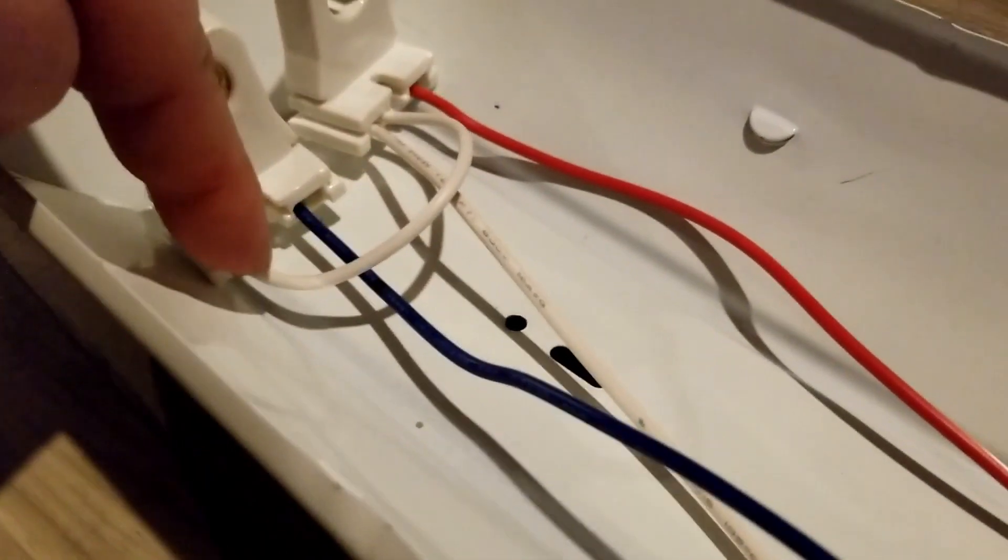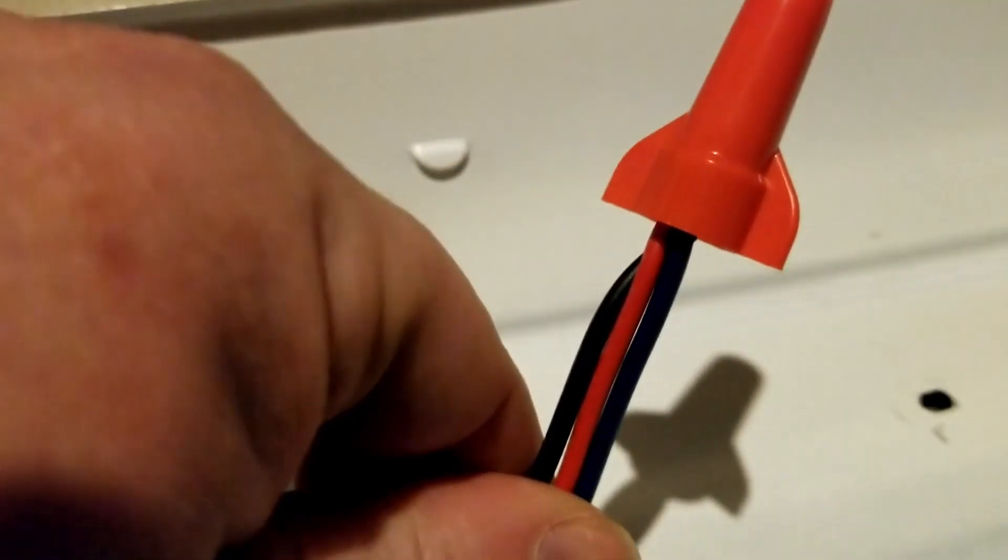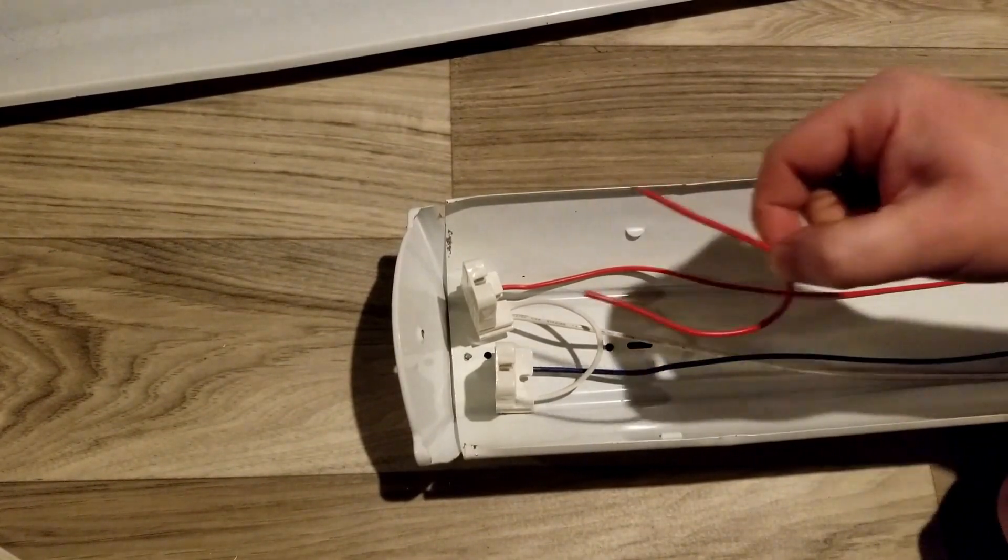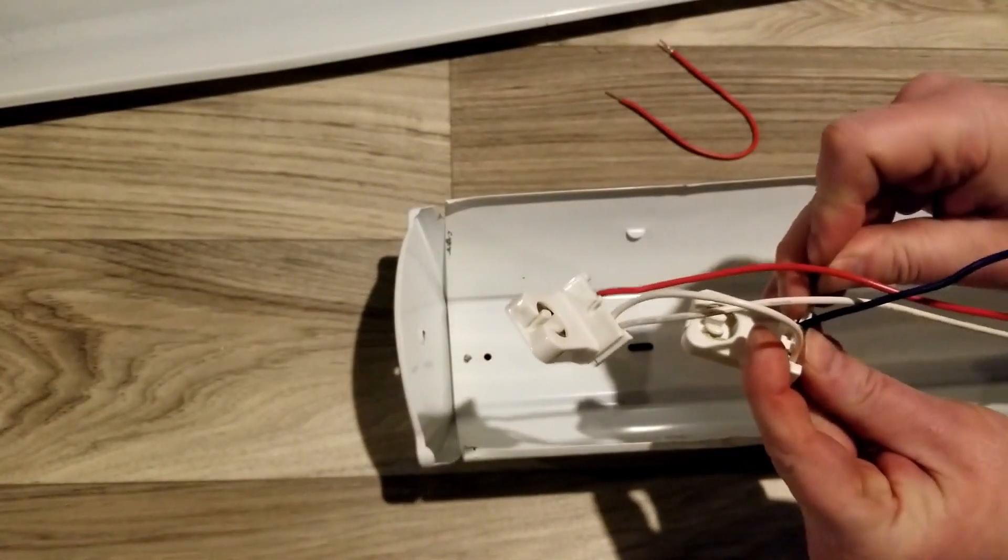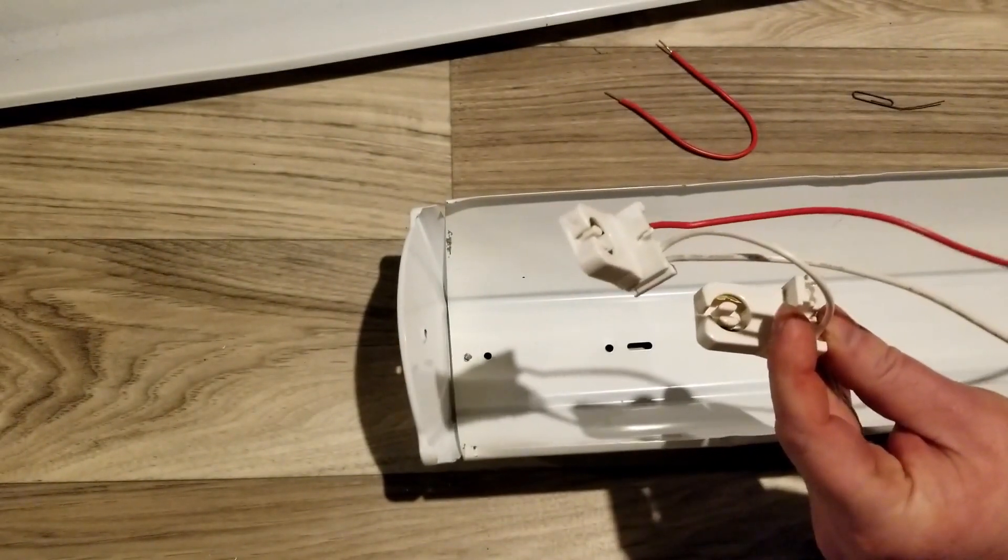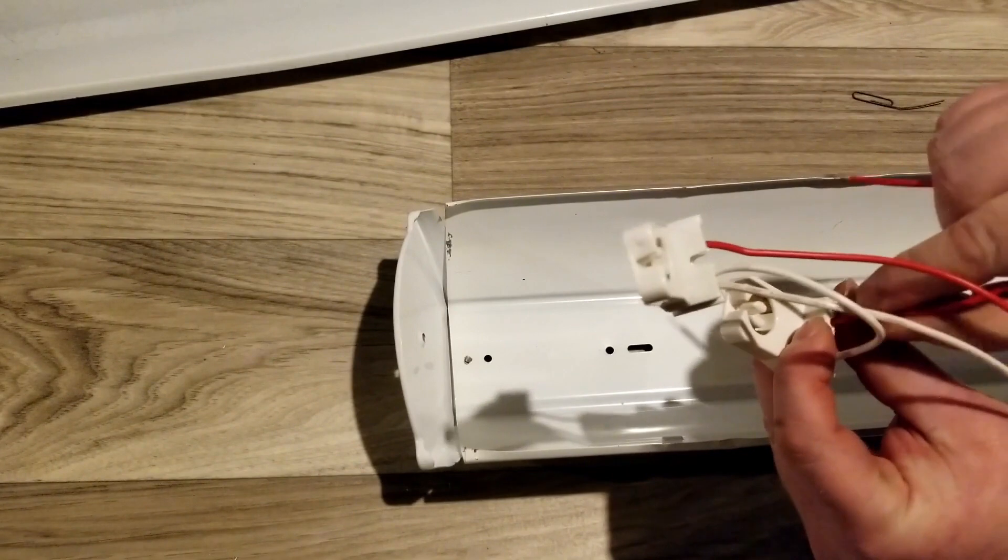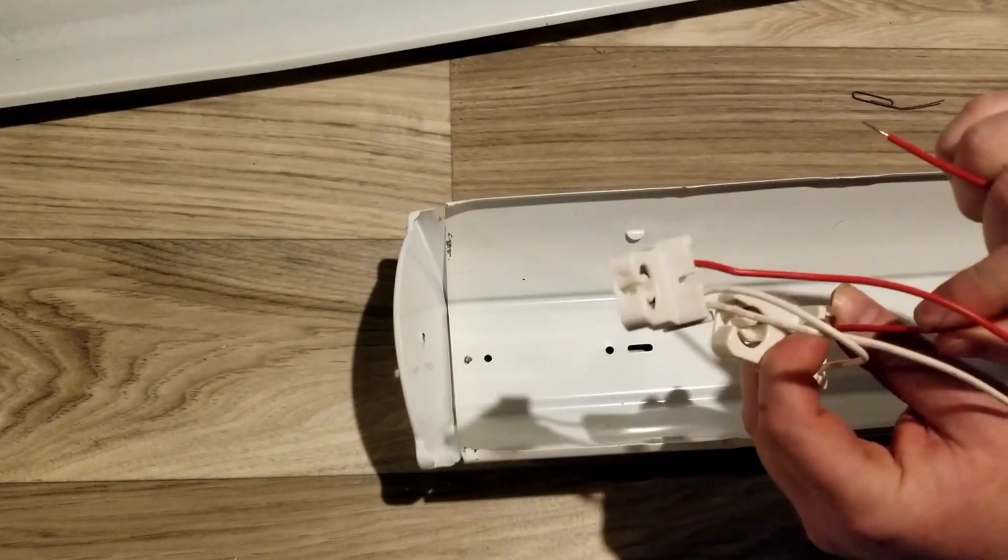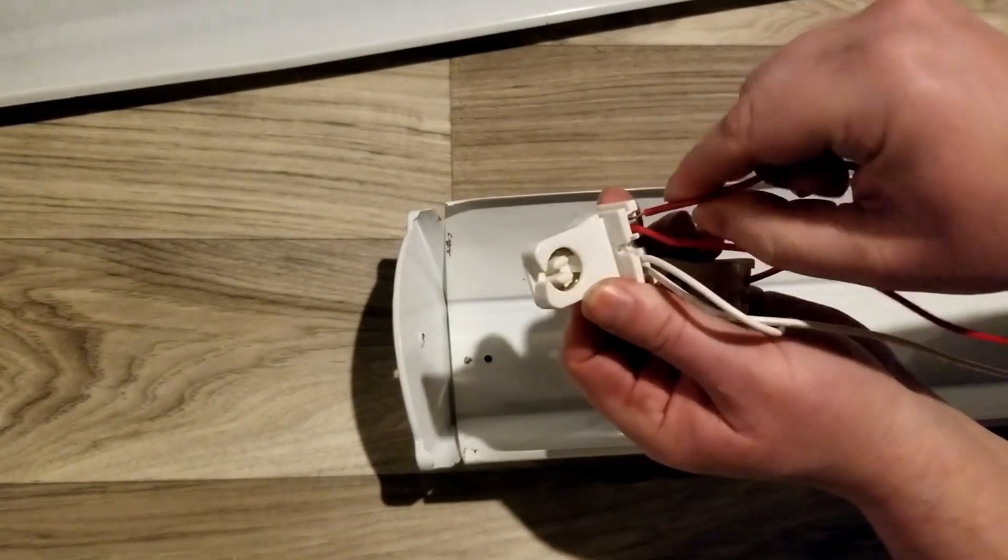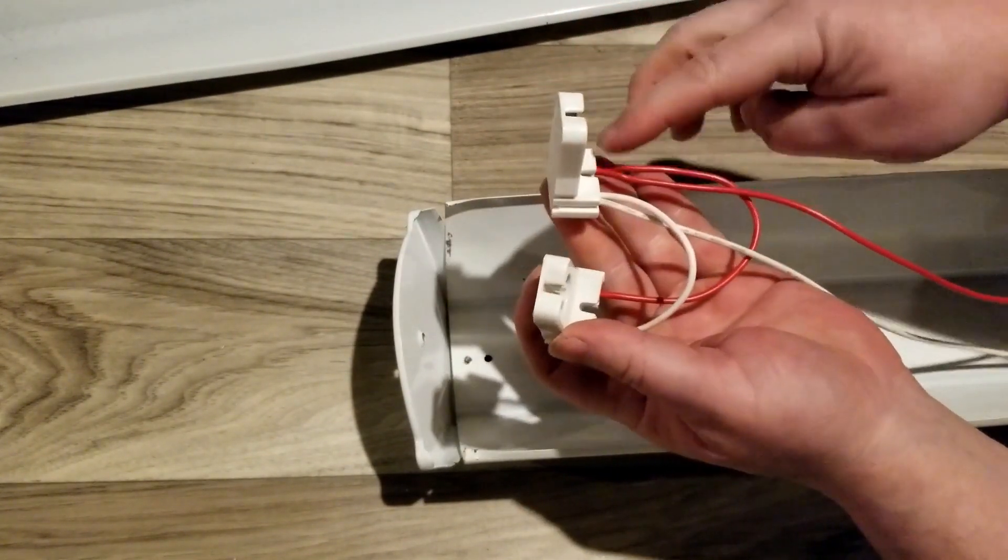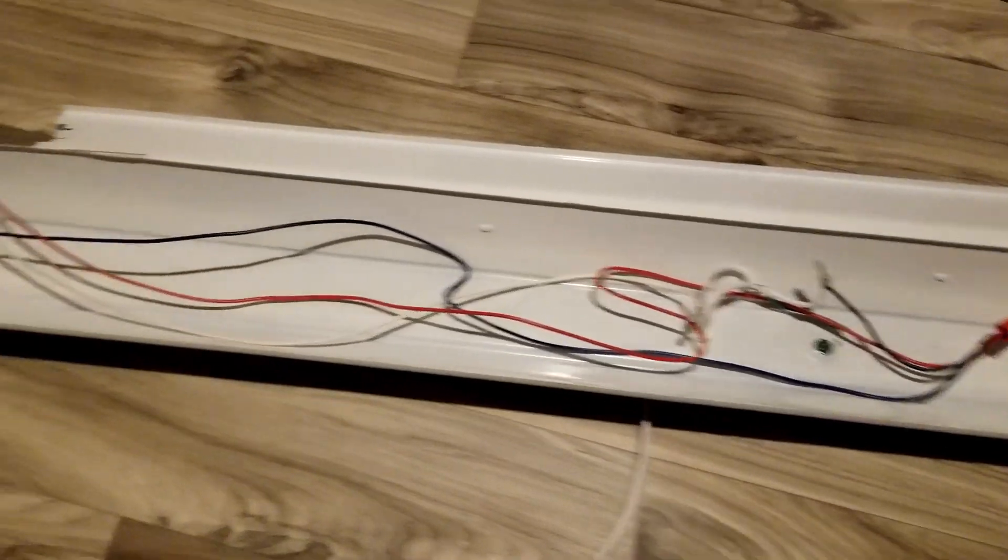Here is one option: these are still in parallel and we take the blue and red wire and put them together with the black wire. This is how you would do the option if you wanted to put in that red wire. Take the blue wire out and totally remove that - take it right out. You would connect in your red wire, be sure to give it a good pull so it latches, and just put it right in the side of that one. Now we have the parallel connection here, so now the wiring is done. That simple - get rid of that ballast.